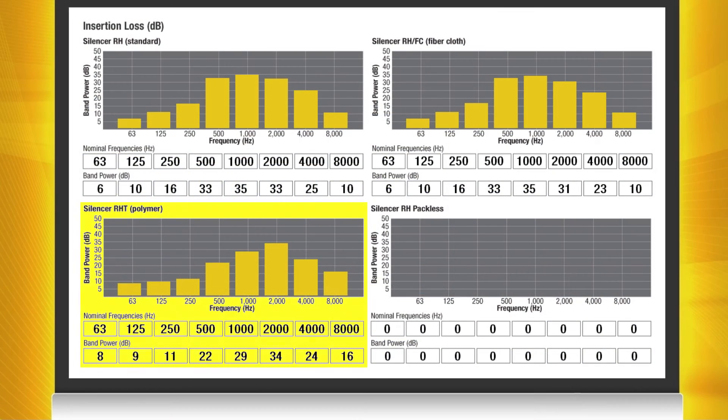You can see that the insertion loss performance of the polymer film lined silencer is less than that of a standard RH silencer. In some cases the film liner is necessary for the application but it's important to note that it does have a negative effect on the acoustical performance of the silencer.